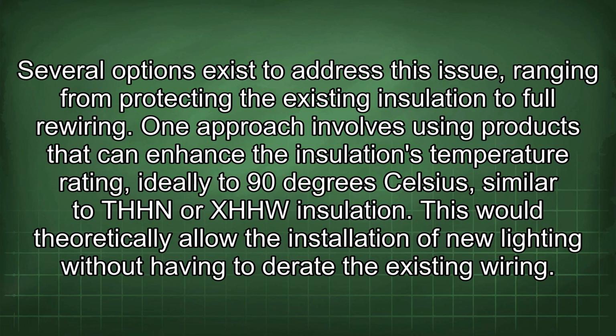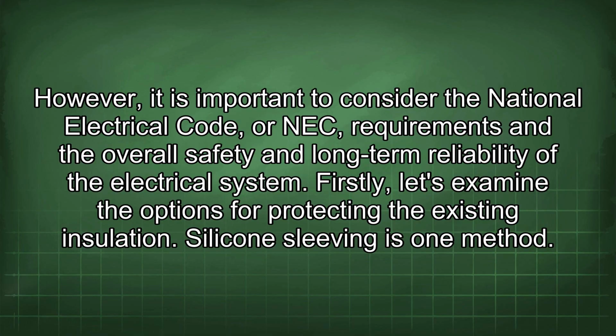Several options exist to address this issue, ranging from protecting the existing insulation to full rewiring. One approach involves using products that can enhance the insulation's temperature rating, ideally to 90 degrees Celsius, similar to THHN or XHHW insulation. This would theoretically allow the installation of new lighting without having to derate the existing wiring. However, it is important to consider the National Electrical Code, or NEC, requirements and the overall safety and long-term reliability of the electrical system. Firstly, let's examine the options for protecting the existing insulation.